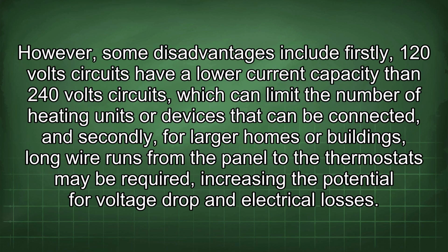However, some disadvantages include: firstly, 120 volt circuits have a lower current capacity than 240 volt circuits, which can limit the number of heating units or devices that can be connected, and secondly, for larger homes or buildings, long wire runs from the panel to the thermostat may be required, increasing the potential for voltage drop and electrical losses.